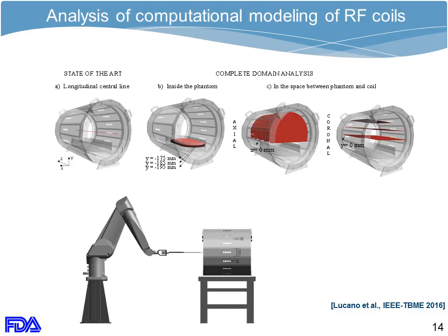In the image on top, you can see the coil. You can see a so-called phantom, essentially a box filled with saline solution, and we measure the electric field in several planes, which are the planes highlighted here in red, both longitudinal planes as well as axial planes. We collected this data of electric field and magnetic field, and we compared those data with the results of the electromagnetic simulations performed with the models that I showed before.